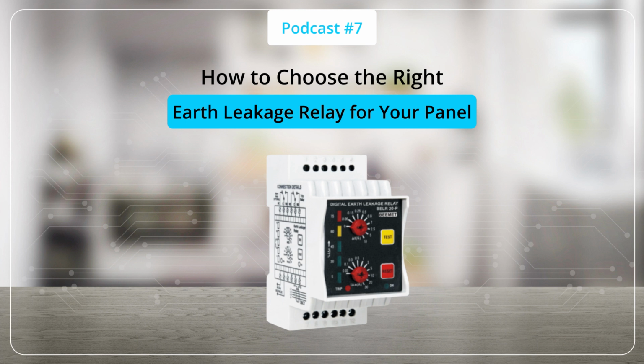ELRs are generally available in three main categories. The first is the analog ELR, which is simple, economical, and suitable for basic protection requirements. The second is the digital ELR, which offers advanced capabilities such as displays, adjustable settings, communication features, and fault logging functions. The third category includes integrated devices, such as RCCBs and RCBOs, which are commonly used in residential electrical systems. Depending on the application, ELRs can offer sensitivity ranges from 30 milliamps up to 30 amps.